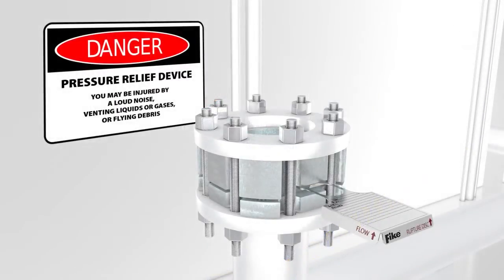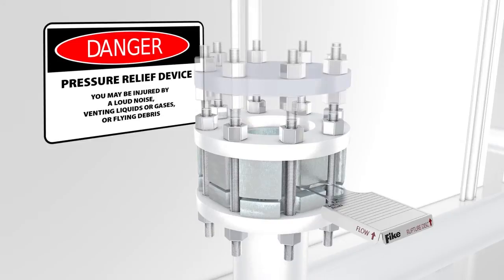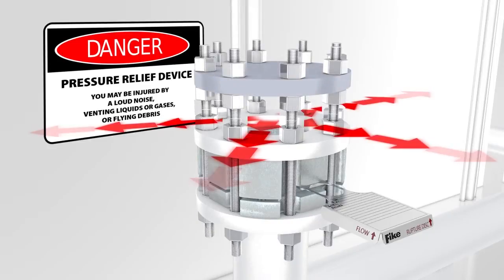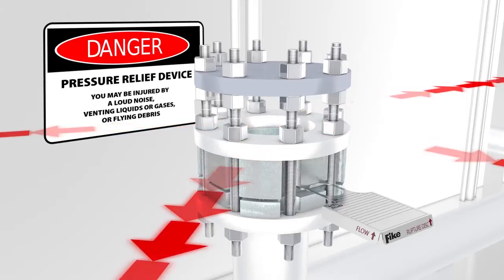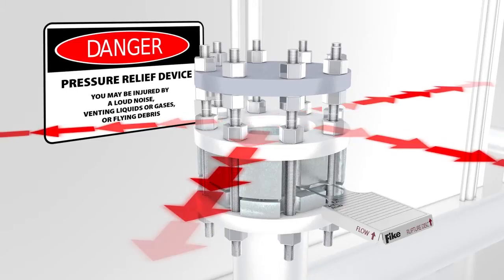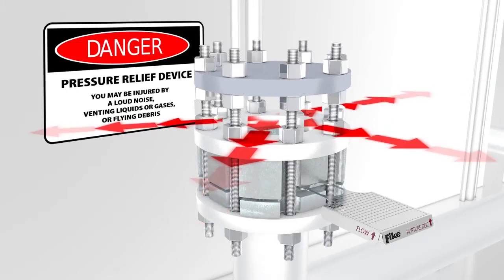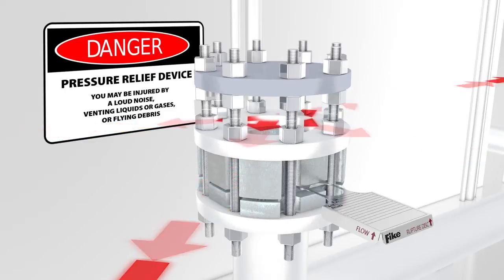Baffle plates used on the end of outlet piping will redirect but not eliminate potentially dangerous system discharge. The piping near the rupture disc assembly should be braced to absorb shock caused by the opening of a rupture disc.